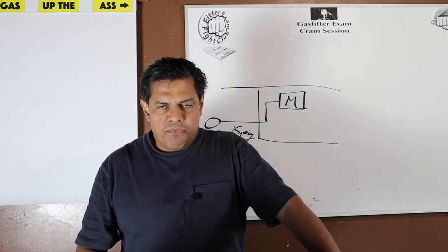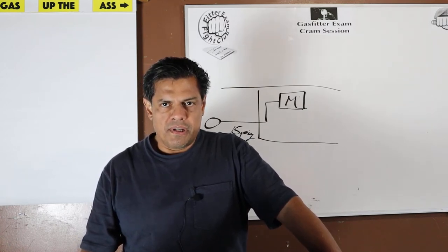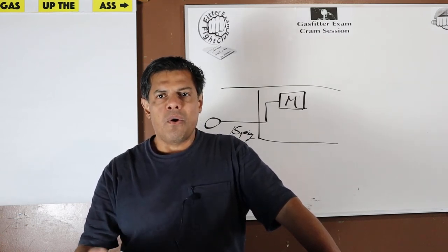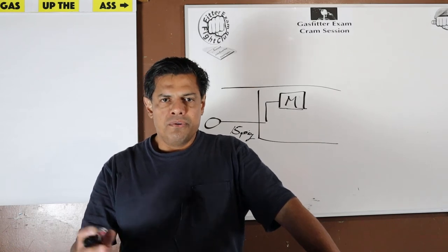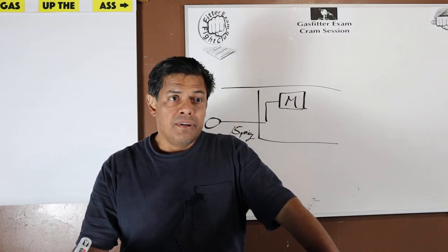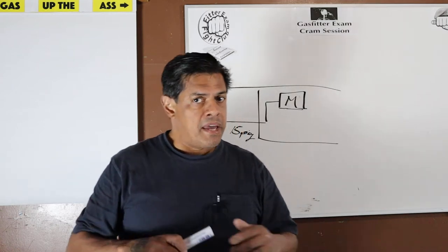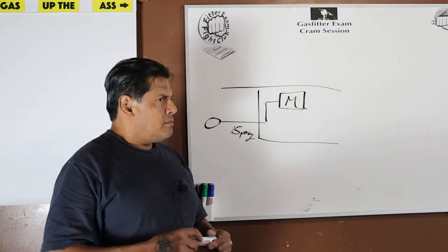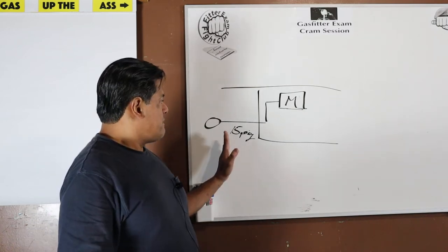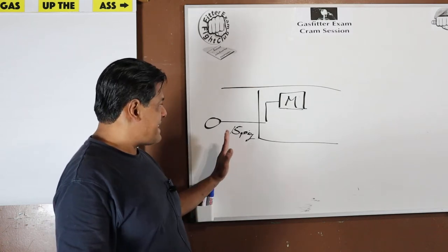I say this because if we look at the mechanical code, which amongst other things deals with steam, high pressure steam is anything over 15 psi. You could have exactly 15 psi in a steam system. That's not high pressure steam. You could have 15.1 psi in a system. Oh, now we have high pressure steam. Gas, no. Everything here says gas is dangerous and we're terrified of it. So, yes, 15 PSI, that's high pressure gas and anything above. It starts at the 15.